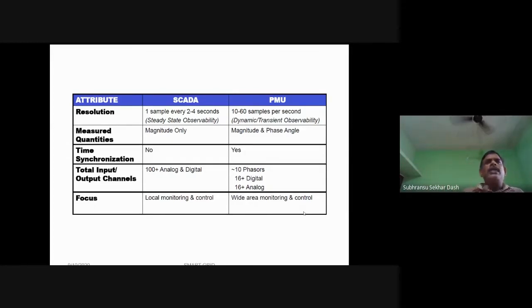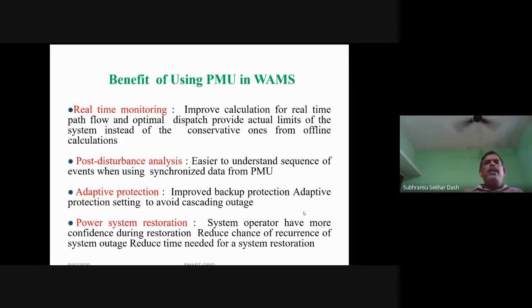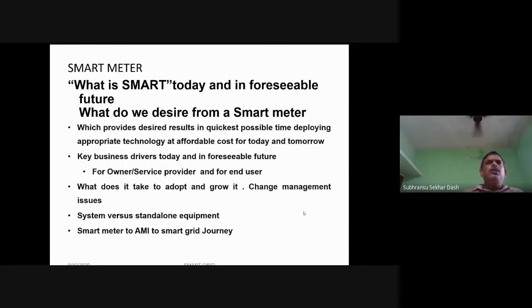In SCADA, there is no time synchronization. In PMU, it is there. In total input output, there are 100 plus analog and digital. Here you can have digital, analog, local. So basically, it is wide area monitoring and control, whereas SCADA is only used for local area. So these are the benefits of PMU: real-time monitoring, disturbance analysis, adaptive protection, power system restoration. Then we will be talking about smart meters for a few minutes, as it is very relevant in the present scenario.